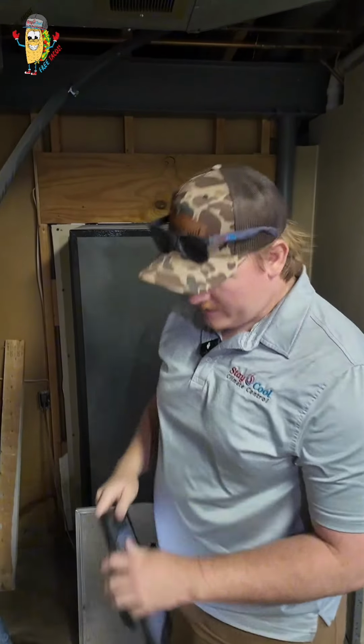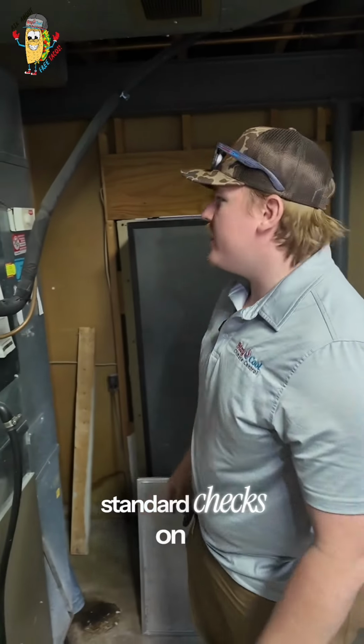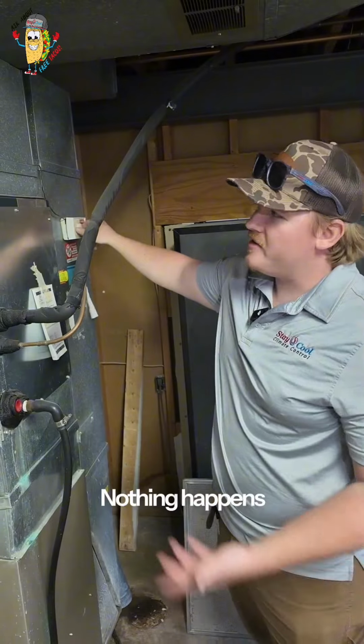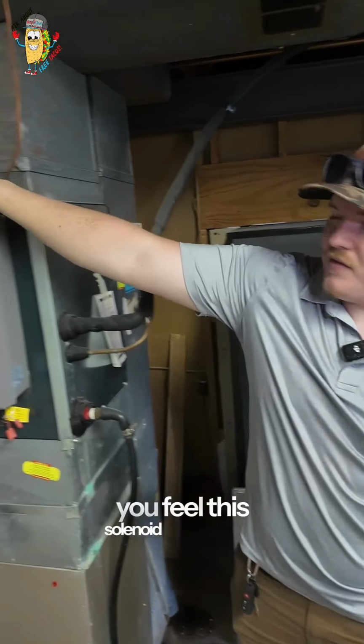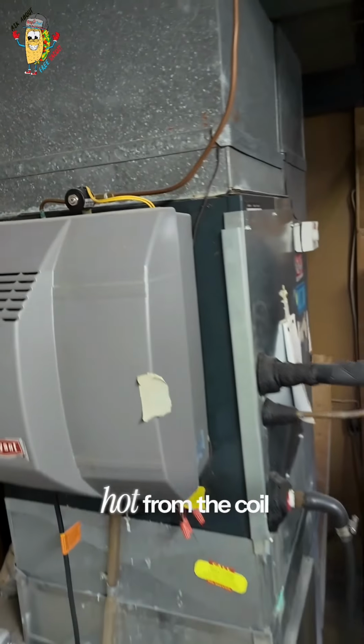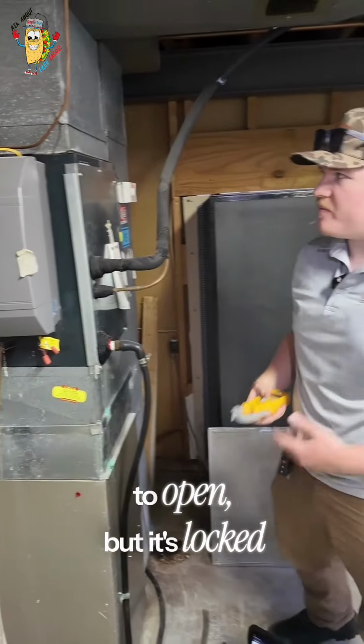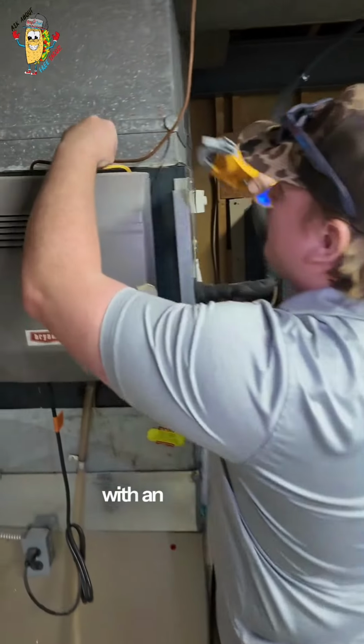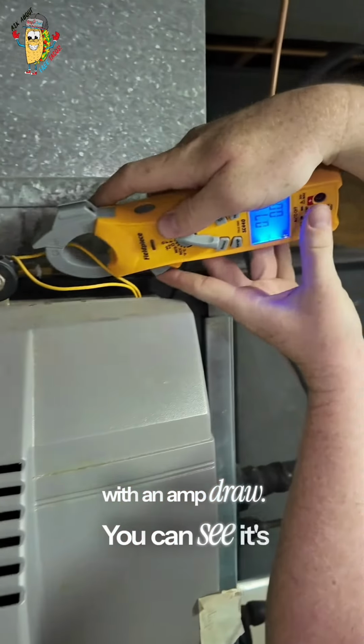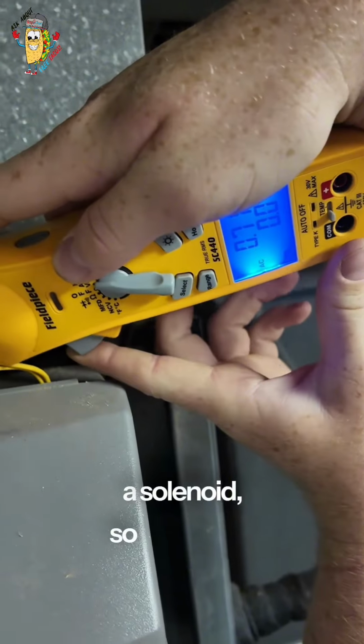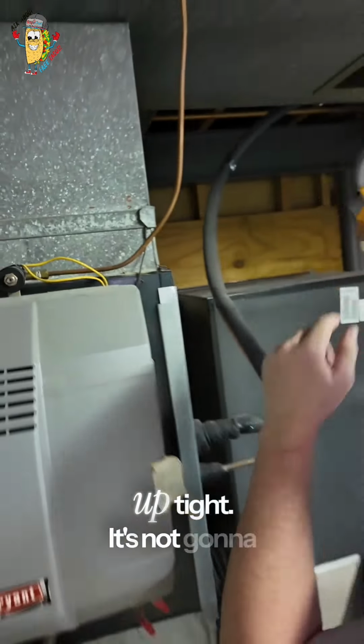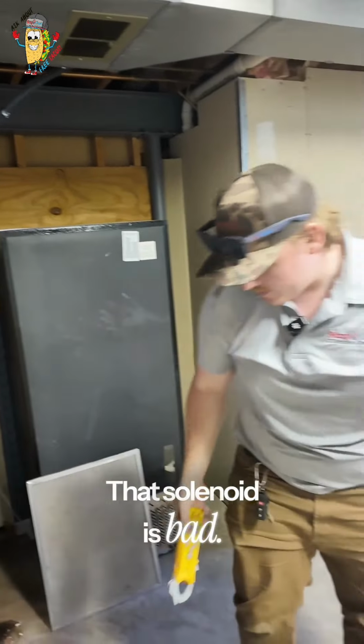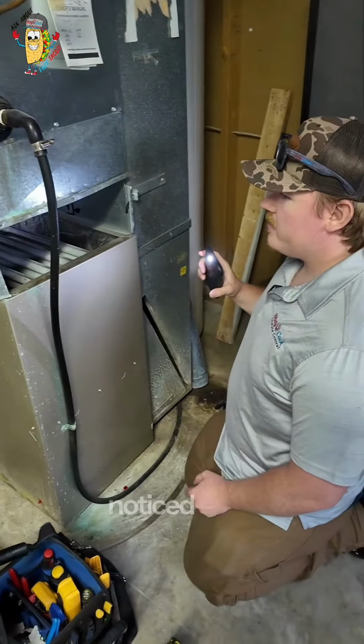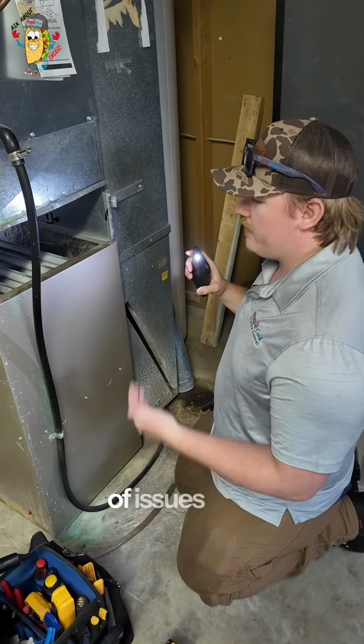So after taking a look at this humidifier, we're doing our standard checks on it, pretty much trying to turn it on. Nothing happens, and you can check. You feel this solenoid is super hot from the coil in there trying to open, but it's locked up. We can even check with an amp draw. You can see it's pulling pretty high amps for a solenoid, so it's locked up tight. It's not going to let any water through. That solenoid is bad.